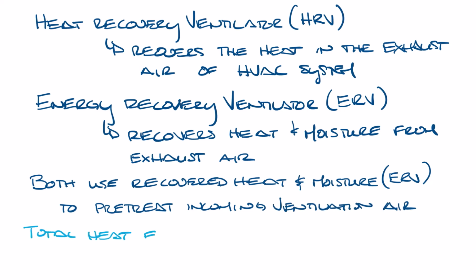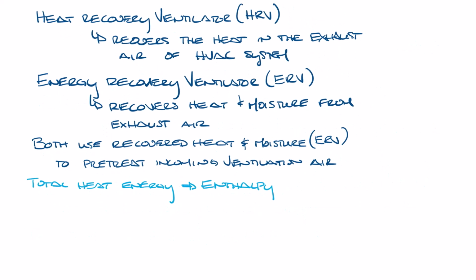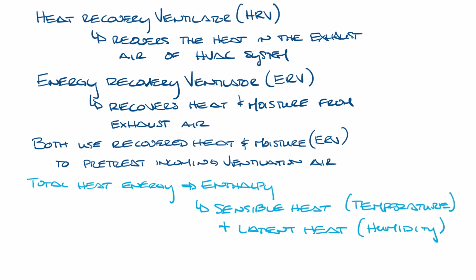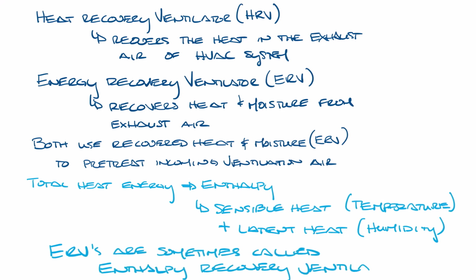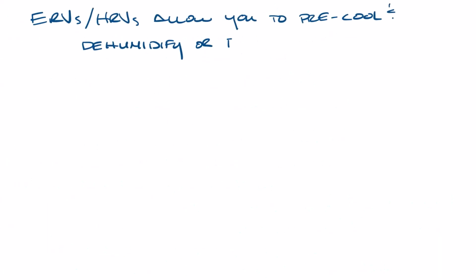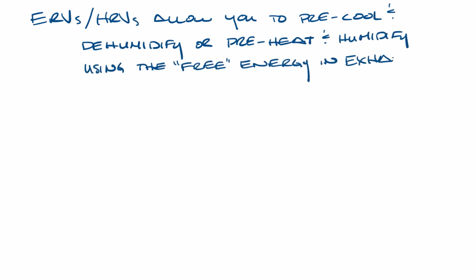The total heat of energy in air is called enthalpy. Let me make a little bit of room. Enthalpy is made up of sensible heat, which is usually thought of as temperature, and latent heat, which we think of as humidity. So ERVs are sometimes also called enthalpy recovery ventilators. Let's move this over. ERVs and HRVs allow you to pre-cool and dehumidify or preheat and humidify using free energy from your exhaust air, which saves you energy and money.